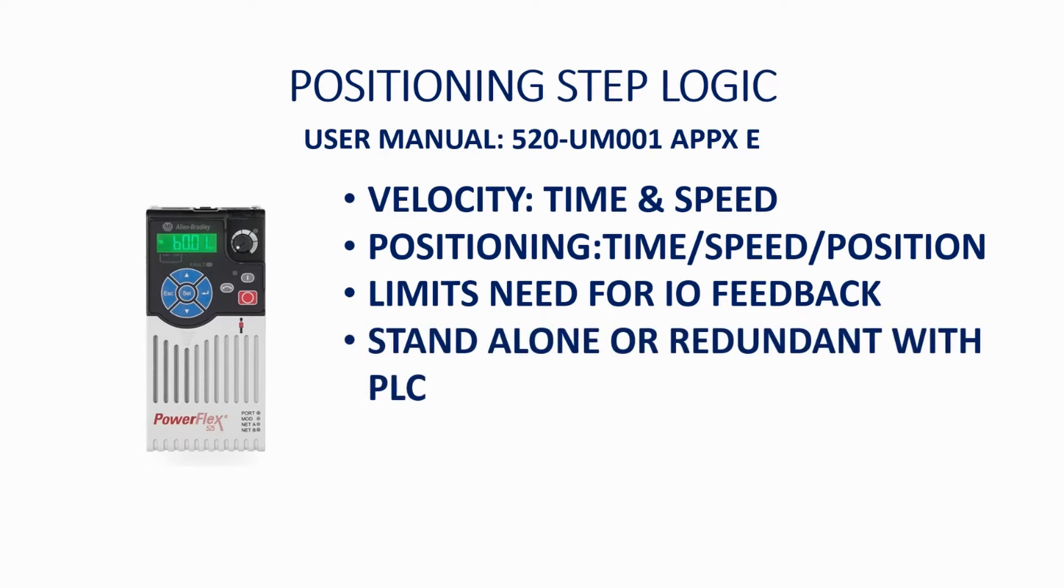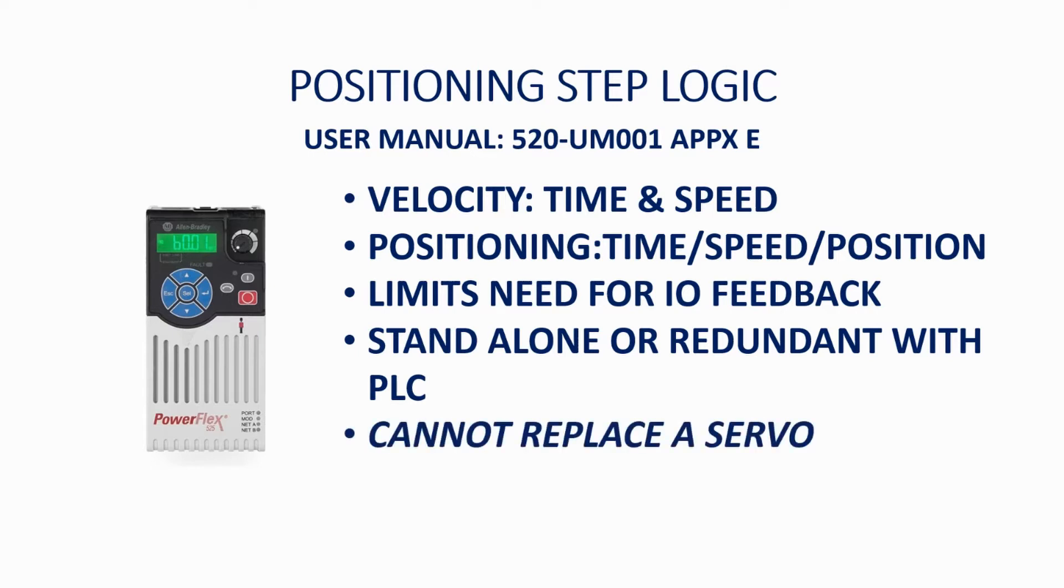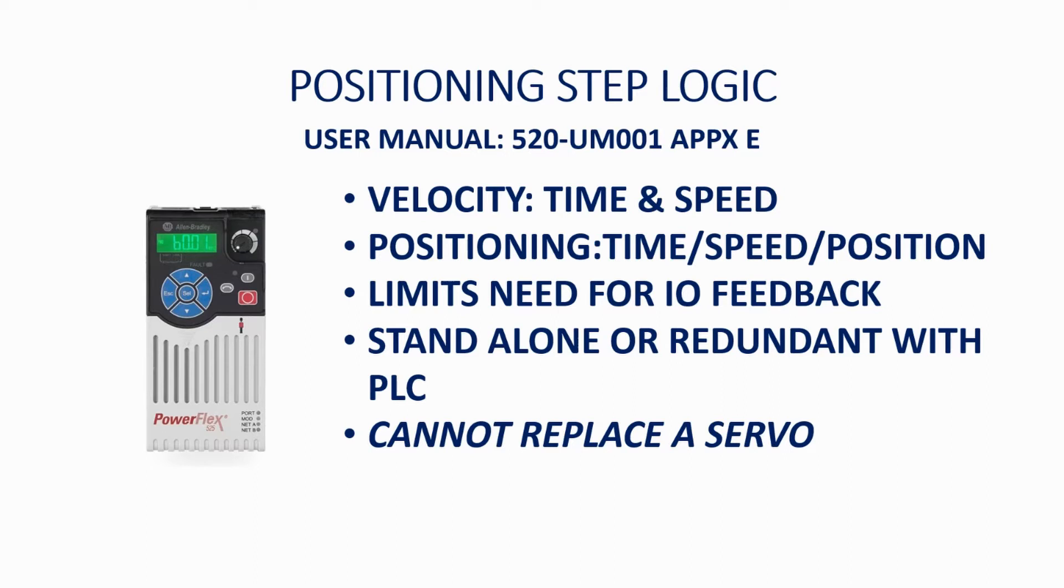This also allows the drive to either stand alone or act in redundancy with the PLC for process control. Please note, a PowerFlex 525 with simple positioning cannot replace a full-blown servo. The PowerFlex 525 lacks the torque regulation, accuracy, and high speed repeatability of a full-blown servo such as a Kinetix 5700.